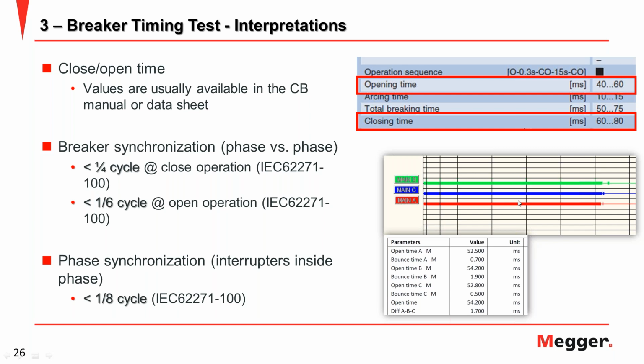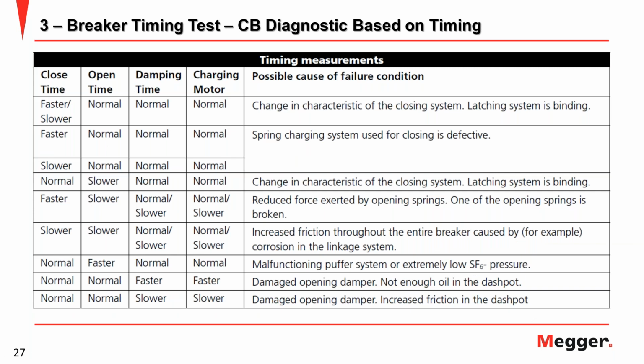And as an example, for the test result from our product, you can see the open time, the difference between phases A, B, C, and also the profile curve, red, yellow, blue, like this. And this is the CB diagnosis based on timing. You can see here what happened and what to be checked if you have a faster close, slower close, or normal open time. So from this table, you can learn to investigate the problem.